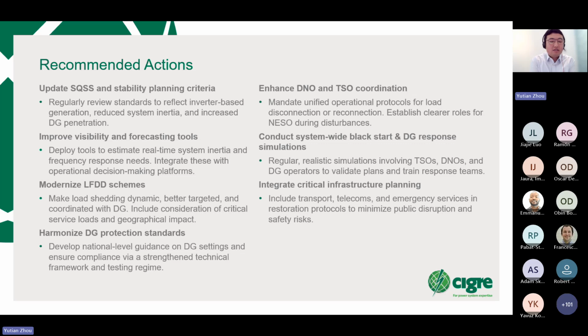First is updating all the standards and stability planning criteria. We need to improve visibility and forecasting tools with the capability of looking at the system's inertia. We need to modernize or upgrade the low frequency demand disconnection schemes. We need to harmonize the distributed generation protection standards, enhance DNO and TSO (transmission system operators) coordination, and also conduct system-wide black start and DG response simulations.